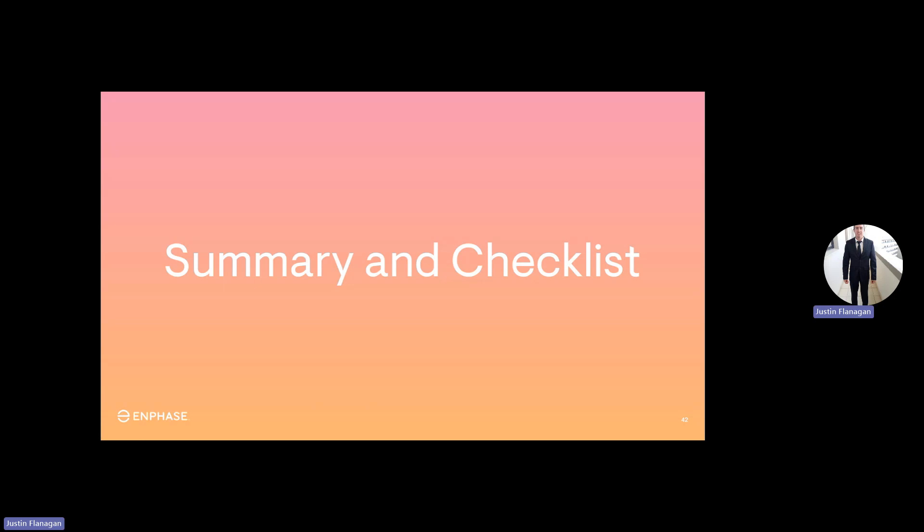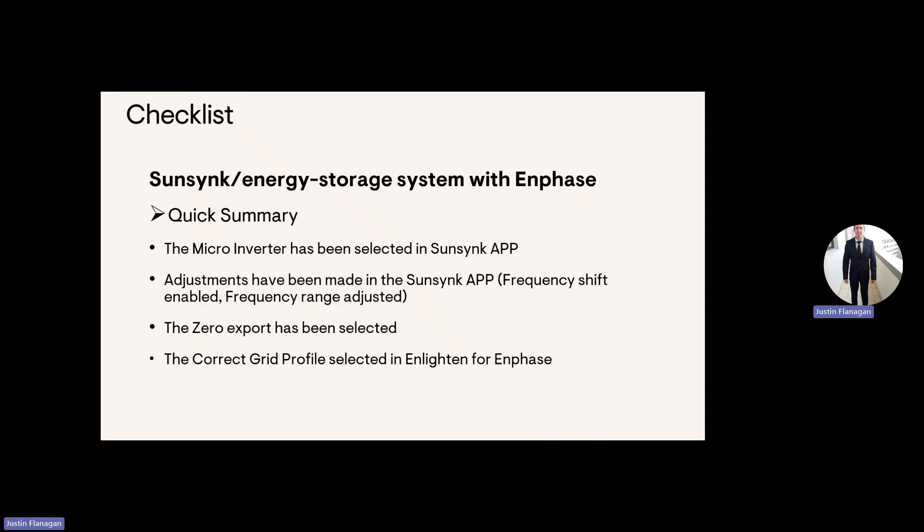Just a summary and checklist. So Sunsynk energy storage with Enphase, the quick summary, the microinverters have been selected in the Sunsynk app. Adjustments have been made in the Sunsynk app. Frequency shift enabled. Frequency range adjusted. The zero export has been selected. And the correct grid profile selected in the Enlighten for Enphase.